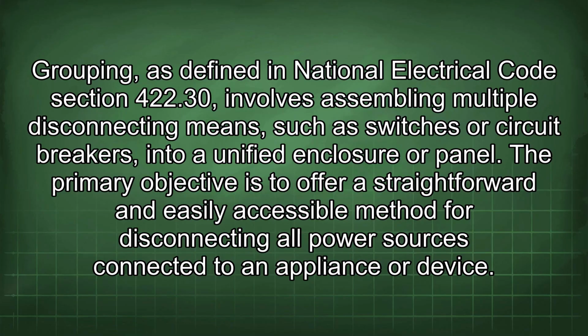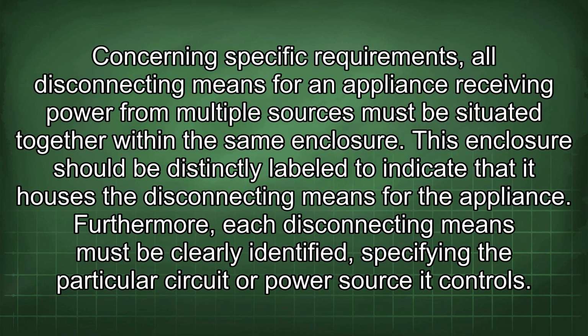Grouping, as defined in National Electrical Code Section 422.30, involves assembling multiple disconnecting means, such as switches or circuit breakers, into a unified enclosure or panel. The primary objective is to offer a straightforward and easily accessible method for disconnecting all power sources connected to an appliance or device. Concerning specific requirements, all disconnecting means for an appliance receiving power from multiple sources must be situated together within the same enclosure.